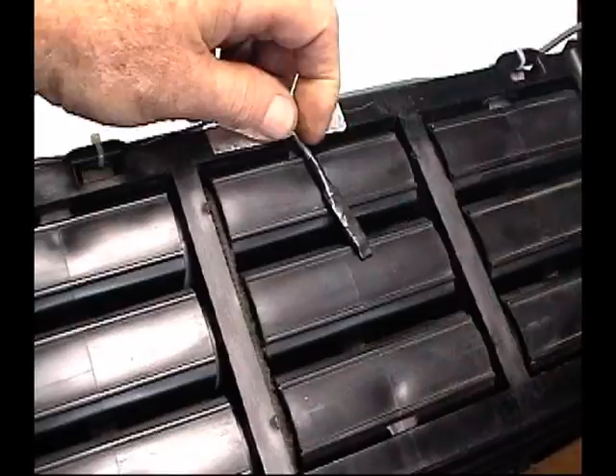You also want to make sure that the little bump on the probe, where the temperature sensor is, is in line with the crack between the cells and is facing outward, so that the inlet air being drawn through there hits the active face of the temperature sensor.